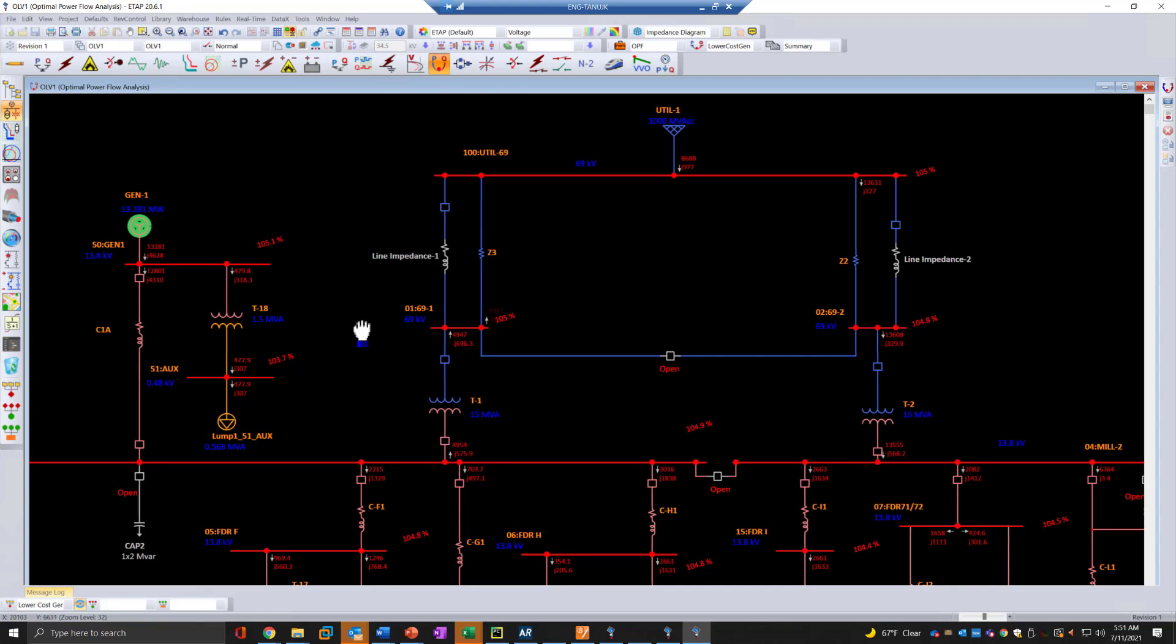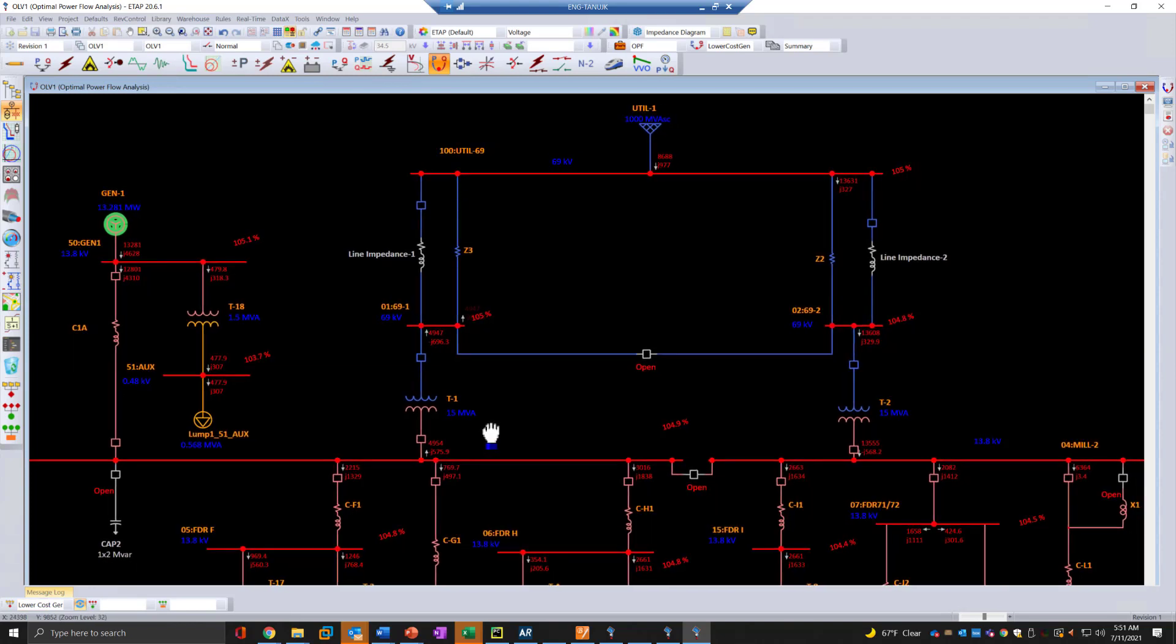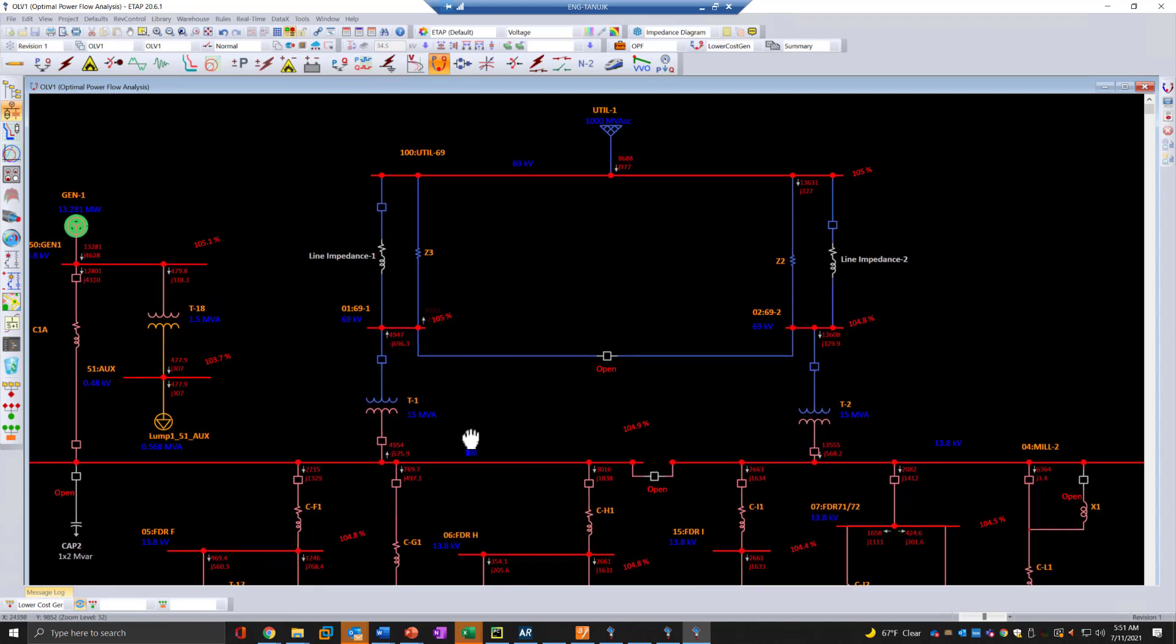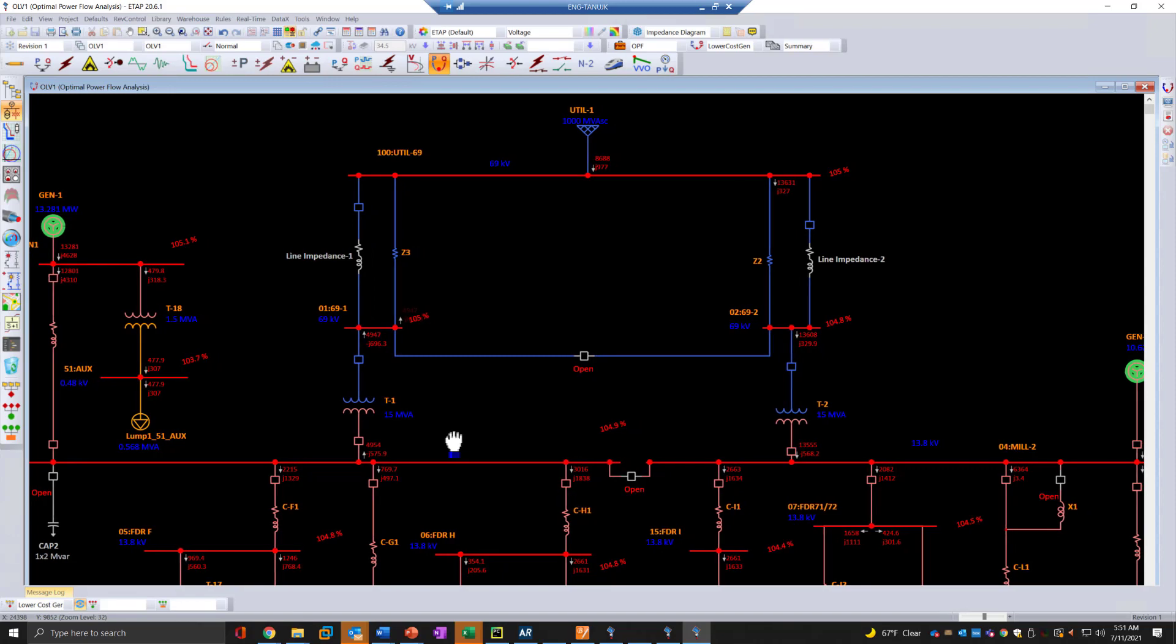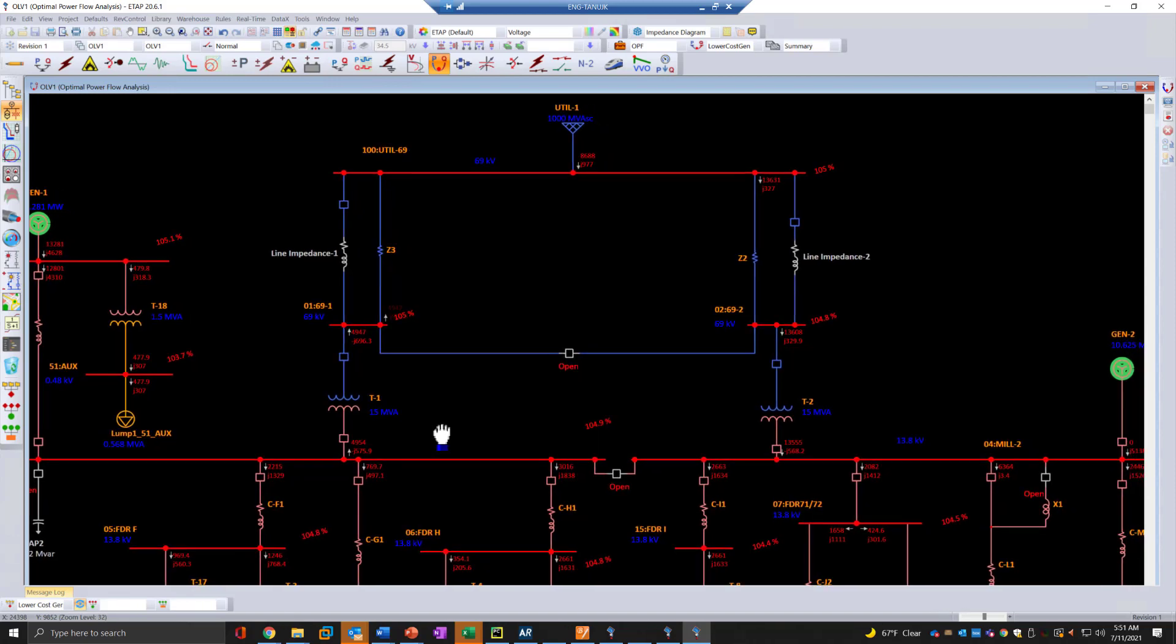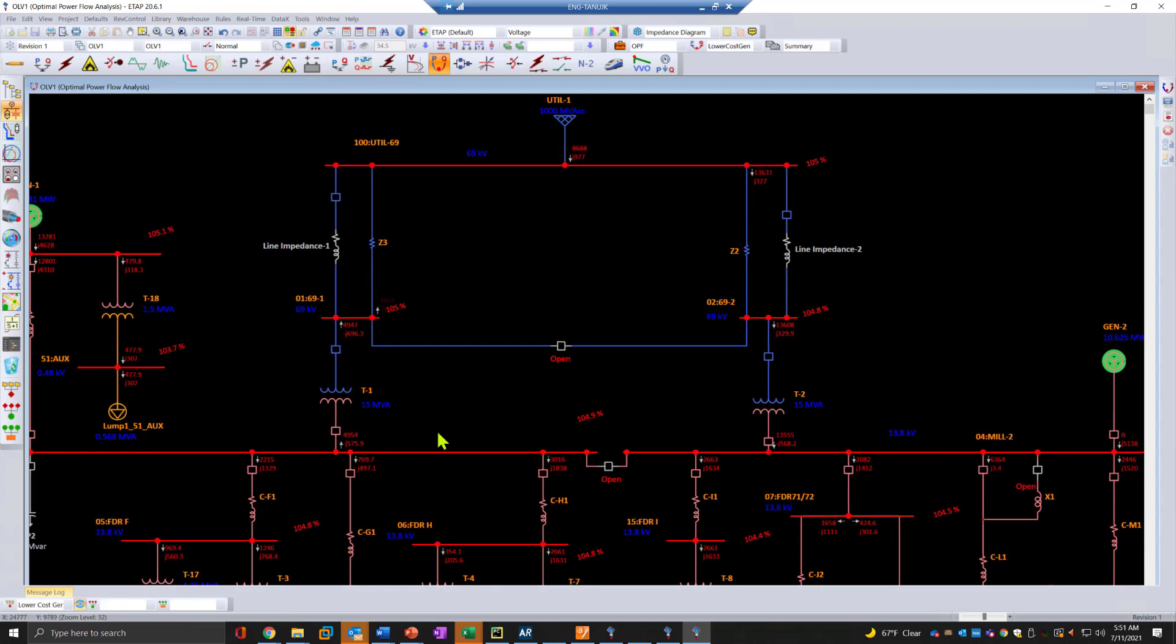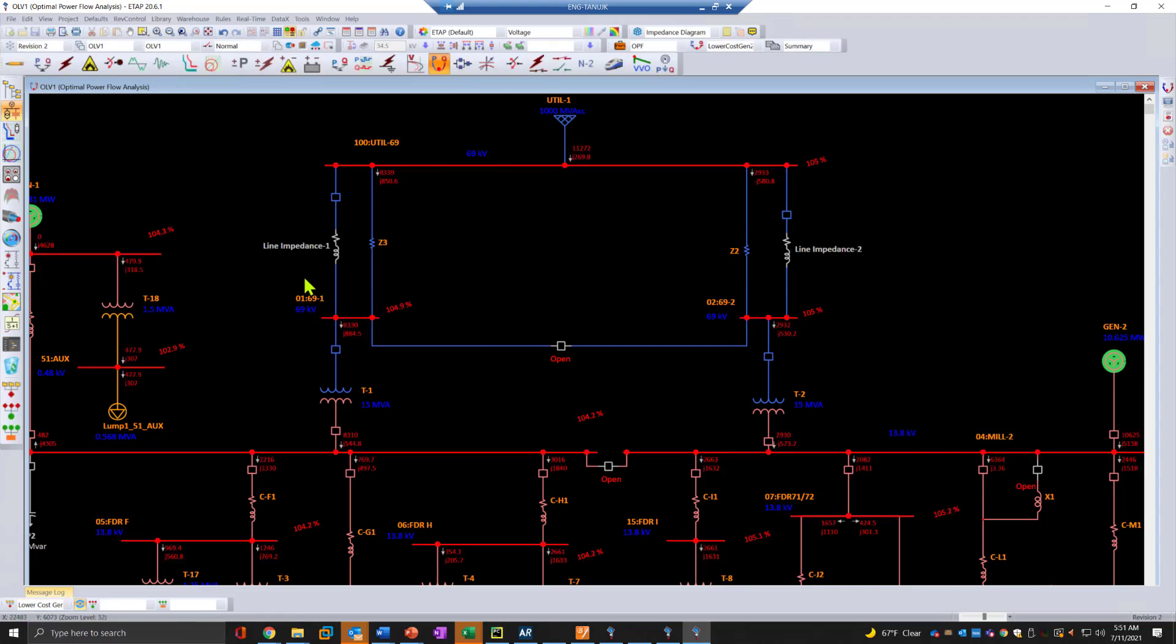This is a case where we are setting up the program such that generator 1 is the cheapest source of energy. You can see how OPF rebalances or redistributes this within the network. When we switch over such that generator 2 now happens to be the cheapest source, you can see generator 1 megawatt going to 0 and generator 2 picking up almost 10 megawatt, while the grid picks up 11.2. This is a case where there's a blend between the energy price on the grid and the generator power.